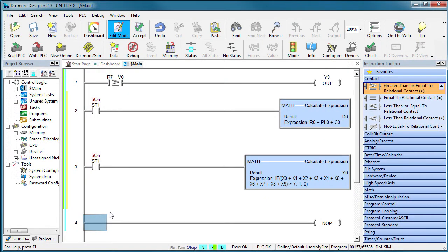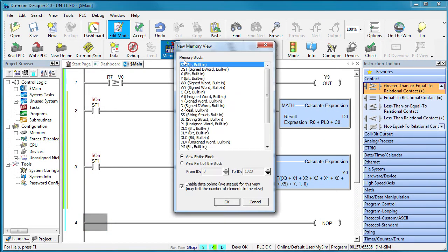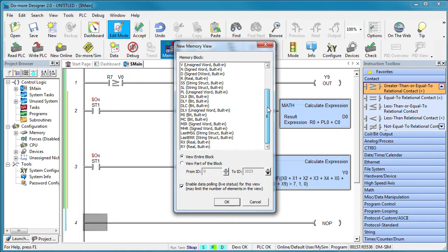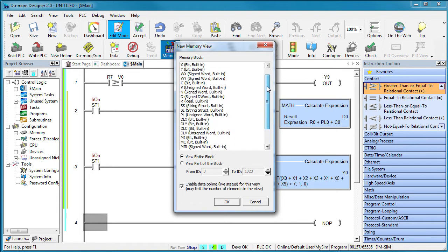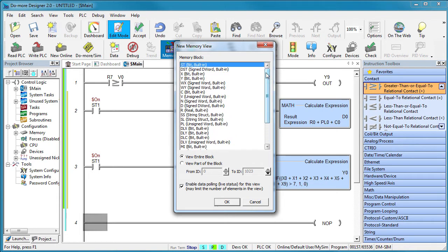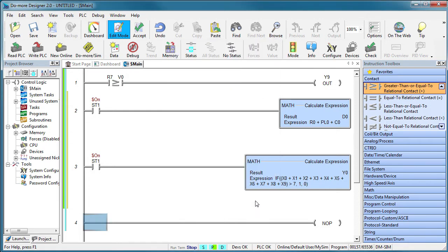Key Thing Number 2: Memory. Like most of today's modern programming languages, DoMore's memory is strongly typed, which means DoMore knows exactly what each memory location is intended to represent. It doesn't have to guess if a particular memory location is an unsigned or signed integer, for example. And because it fundamentally knows what each memory type represents, you can do things like compare a real number with an integer.